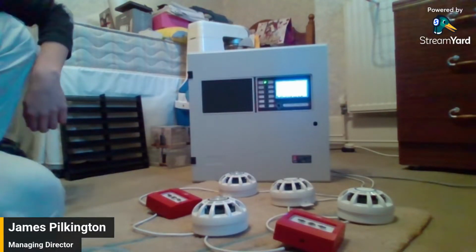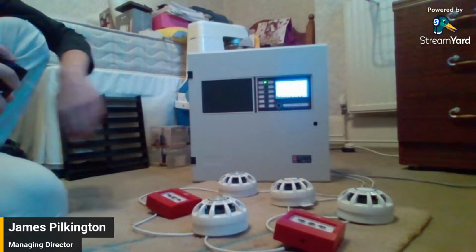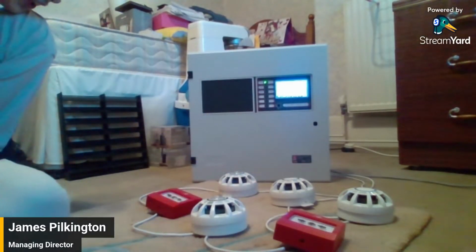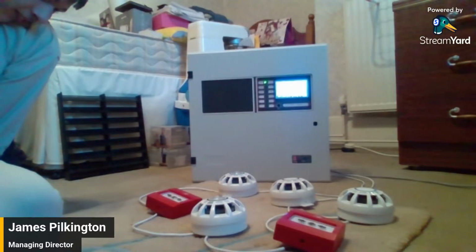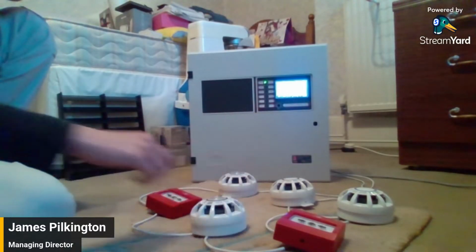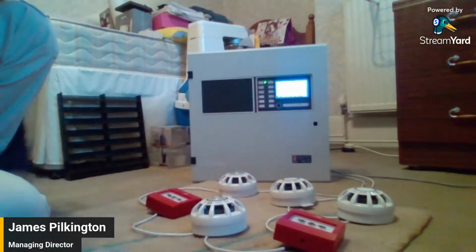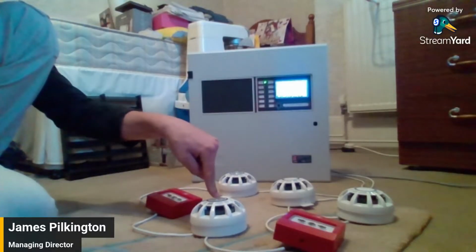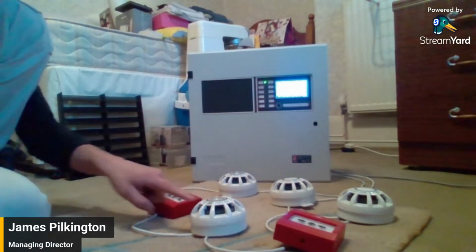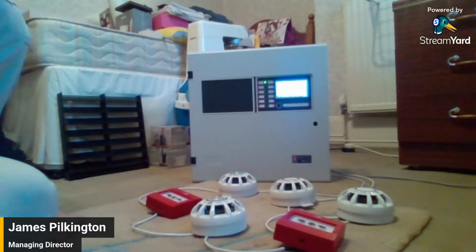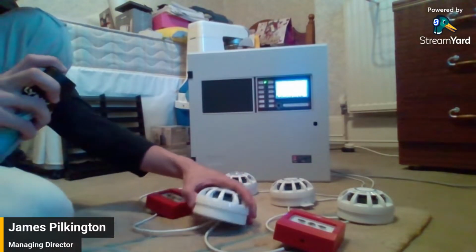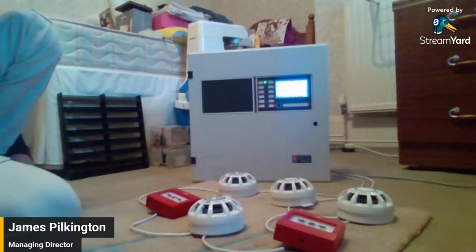It is definitely a resilient detector when it comes to resisting false alarms. I need a solo tester, the ones that can cup the detectors, because these are so false alarm tolerant that using the can smoke can take a while. So eventually it will go. It's just being stubborn.